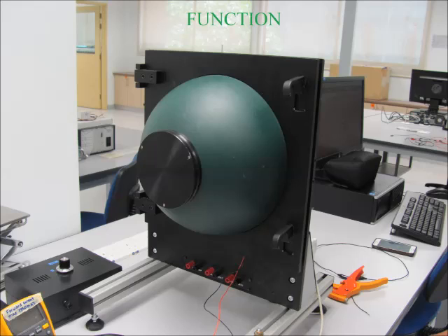Light rays incident on any point on the inner surface are, by multiple scattering reflections, distributed equally to all other points. The effects of the original direction of light are minimized. An integrating sphere may be thought of as a diffuser, which preserves power but destroys spatial information.